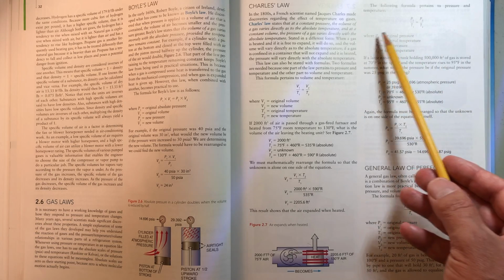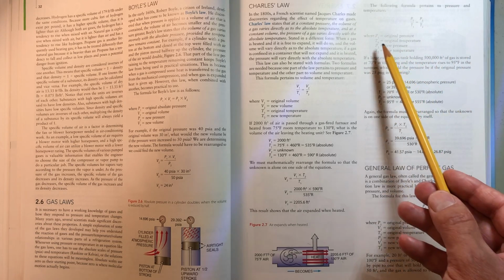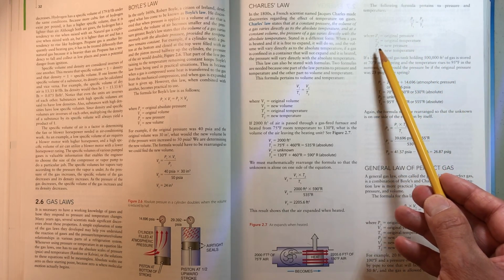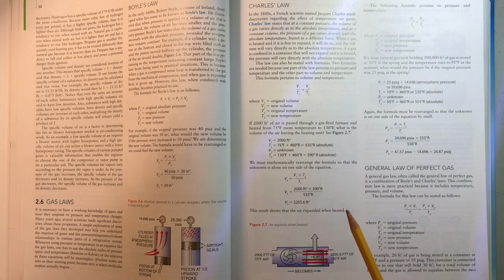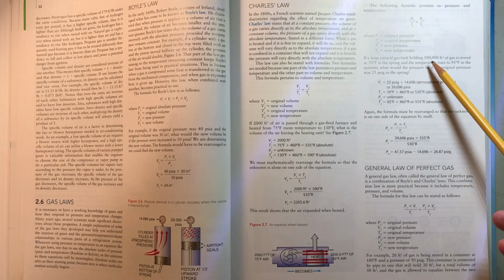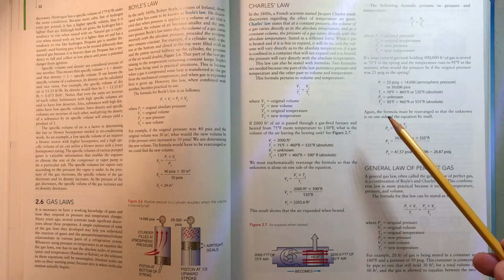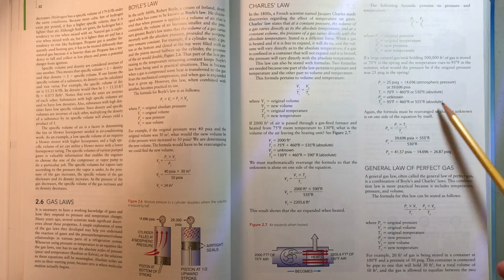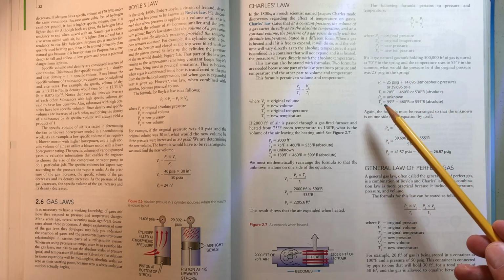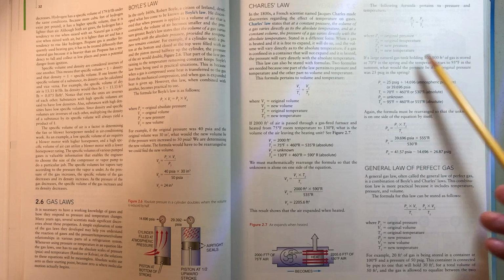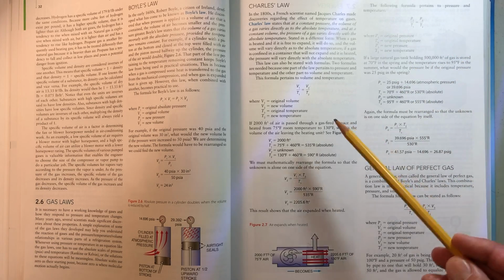So we have one pressure, our original one, and we divide that by the temperature that pressure has a relationship with, and we're going to get a new pressure when we change the temperature to a new temperature. So if we have a large natural gas tank holding 500,000 cubic feet of gas stored at 70 degrees, and the spring temperature rises to a 95 degree day in the summer, that gas is going to want to expand, and we need to make sure that we have enough room for it to expand or the correct vessel that can handle the new pressure.